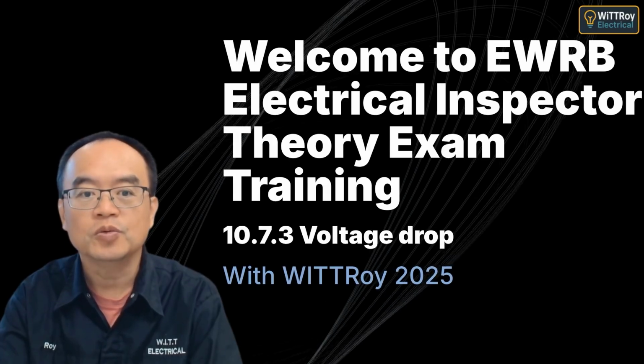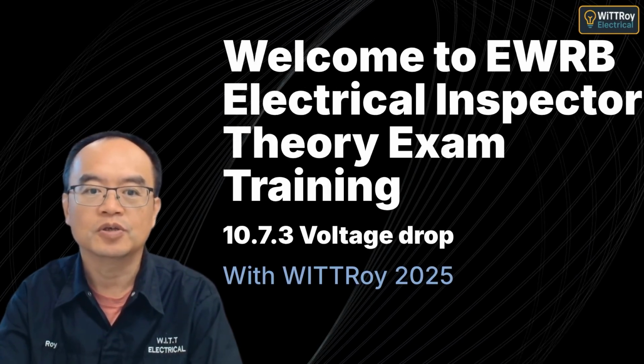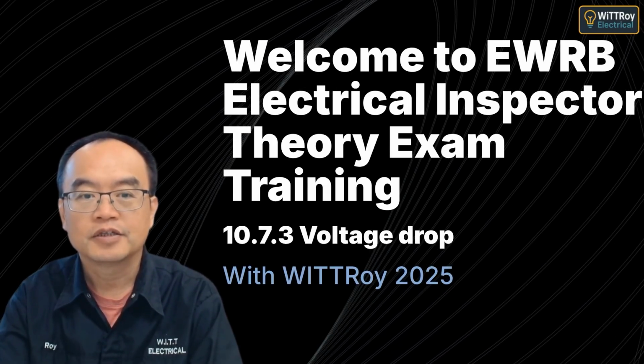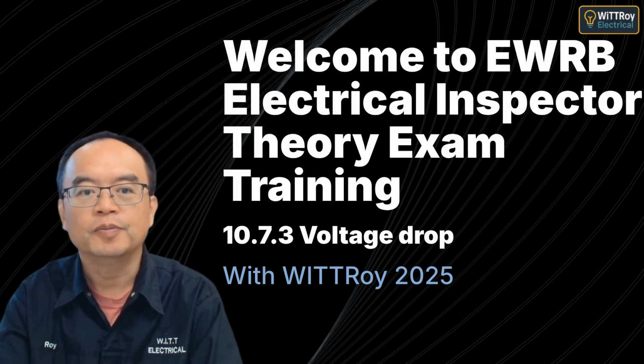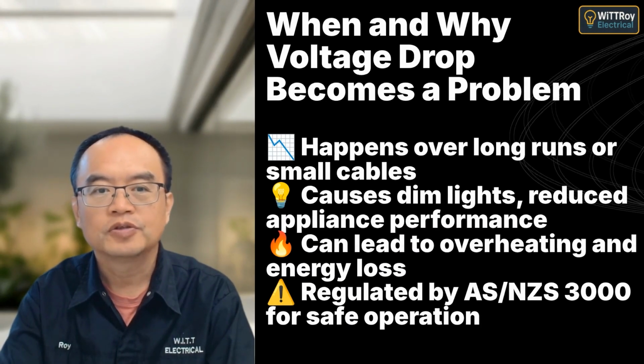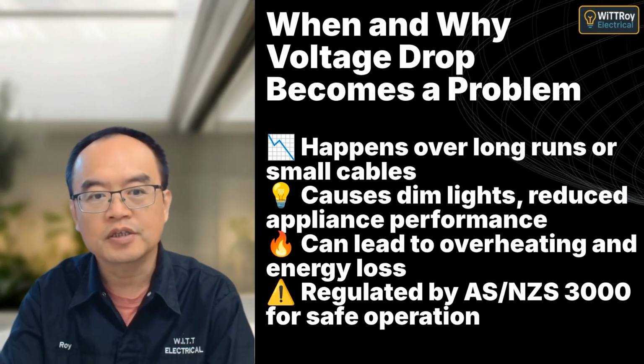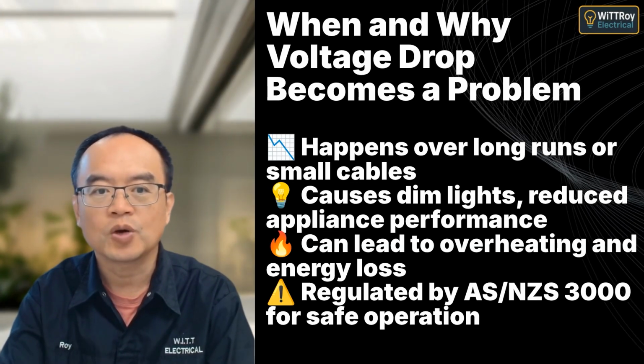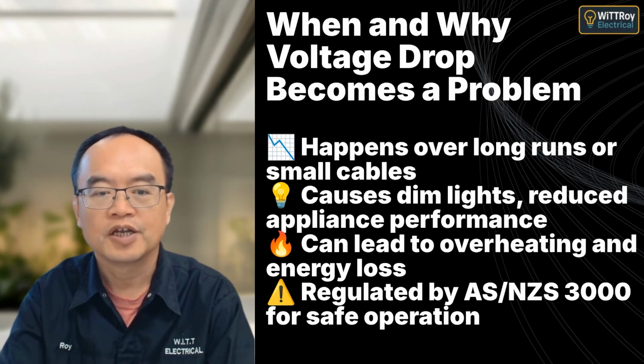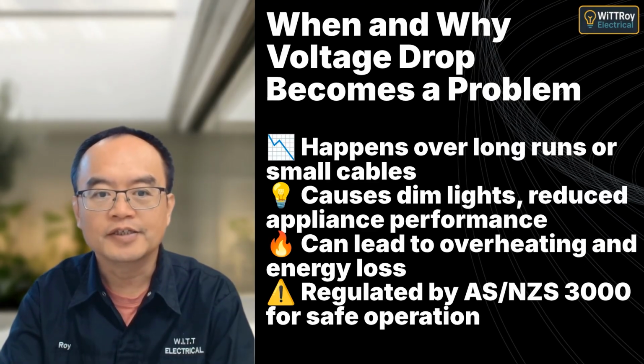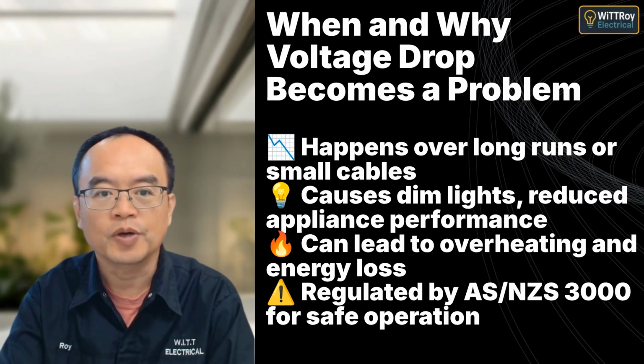In this short lesson, we'll look at voltage drop, where it happens, what affects it, how to calculate it, and how to choose the right cable to keep it within limits. Voltage drop occurs when cables are too long, too thin, or overloaded. It causes lights to dim and equipment to underperform and can even damage motors. AS/NZS 3000 sets limits to keep equipment working safely.